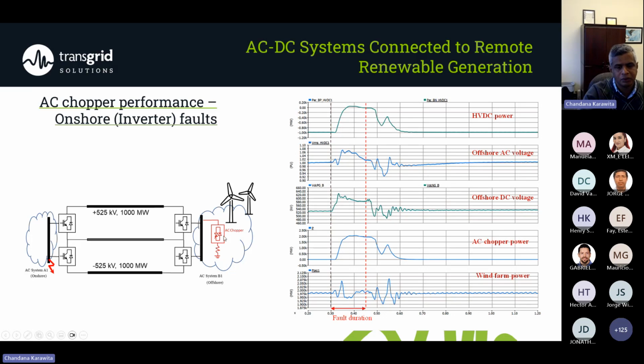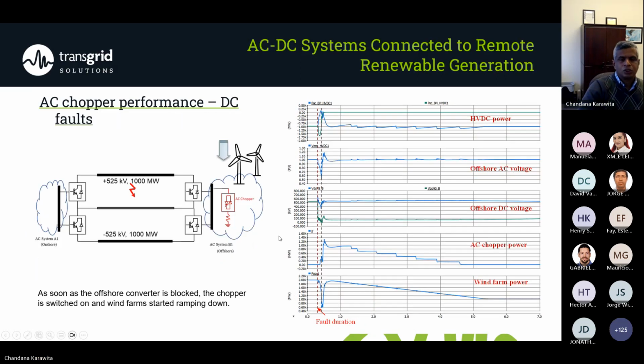But there is an added advantage of the AC chopper. For DC faults, if you have a DC chopper, there is nothing it can do, and we have to trip it as well. But if we have an AC chopper during the DC fault, we can absorb the excess energy using the AC chopper and keep the system stable. So let's say we have a permanent DC fault here: we absorb the energy during the transient, and then order some of the wind farms to trip in order to keep the power balance. But tripping is not the only solution available.